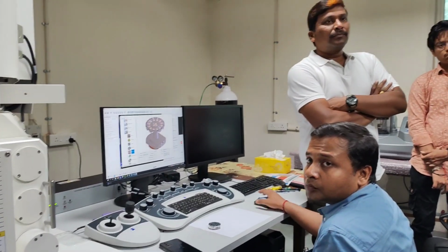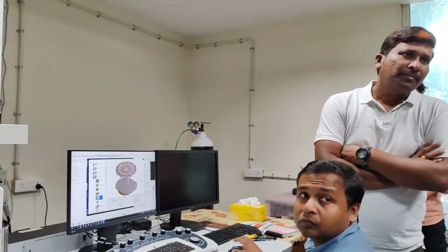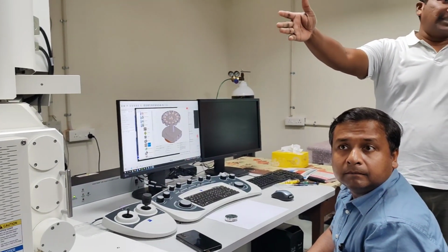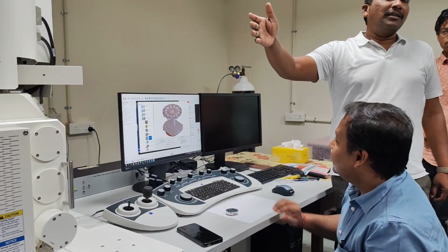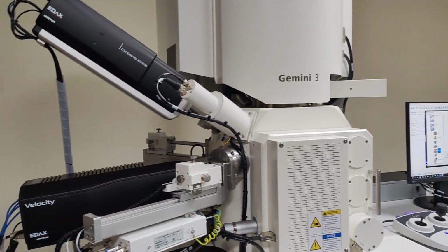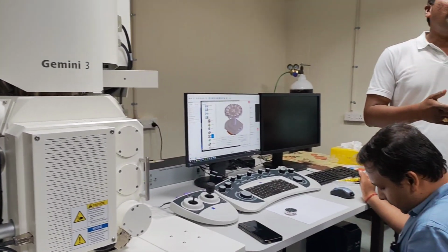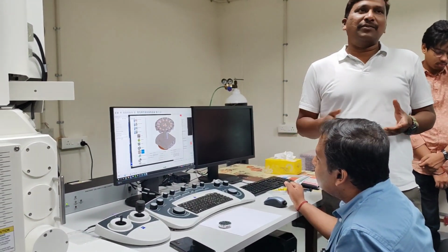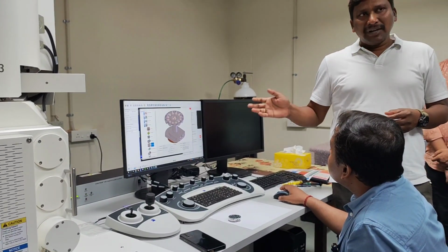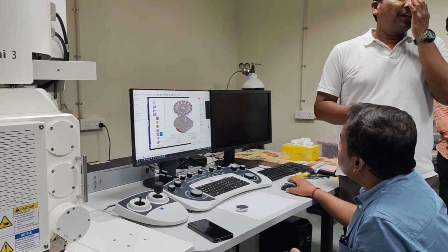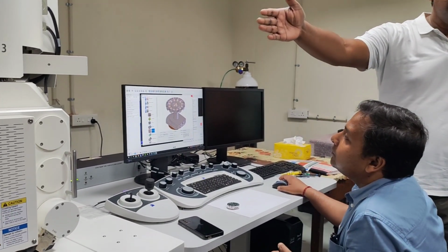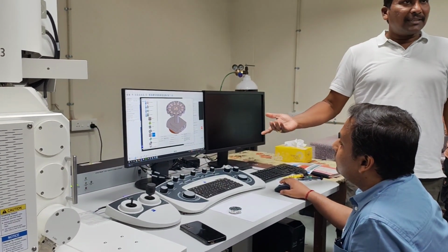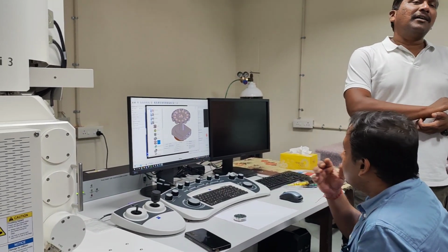Sir, if our sample is amorphous, then what will be the approach to record these images? No, whether it is crystalline or not matters only for EBSD, when you go for crystallography information. For the imaging part it doesn't matter. The only thing is whether it is a conducting or non-conducting sample, and how to handle it with different parameters. Whether it is amorphous or crystalline in nature, for imaging the surface it's something different. Only when you go for EBSD, where you are going to read the crystallography information or the electron channeling contrast, that nature matters.